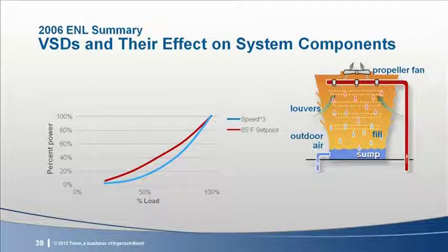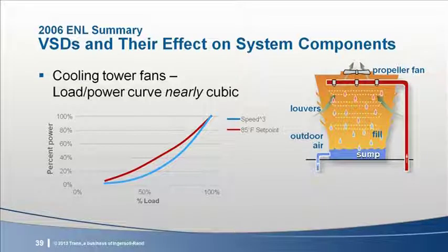Cooling towers are free discharge devices. The air path resistance is almost totally due to frictional losses. There is no fixed lift or variable dampers to influence the airflow resistance. Even so, the power draw of a cooling tower fan does not exactly decrease to the cube of the tower load. The blue line on the chart represents the fan power decreasing to the cube of the fan speed. The red line represents an example of a cooling tower's actual performance if controlled to an 85-degree set point, which would reduce the fan speed as quickly as possible. As you can see, it's close to the ideal performance, but not quite that good.